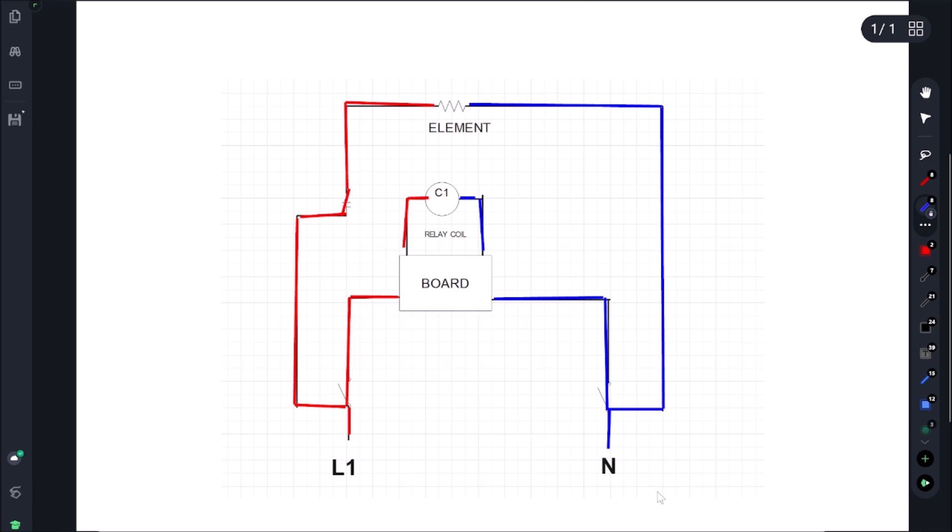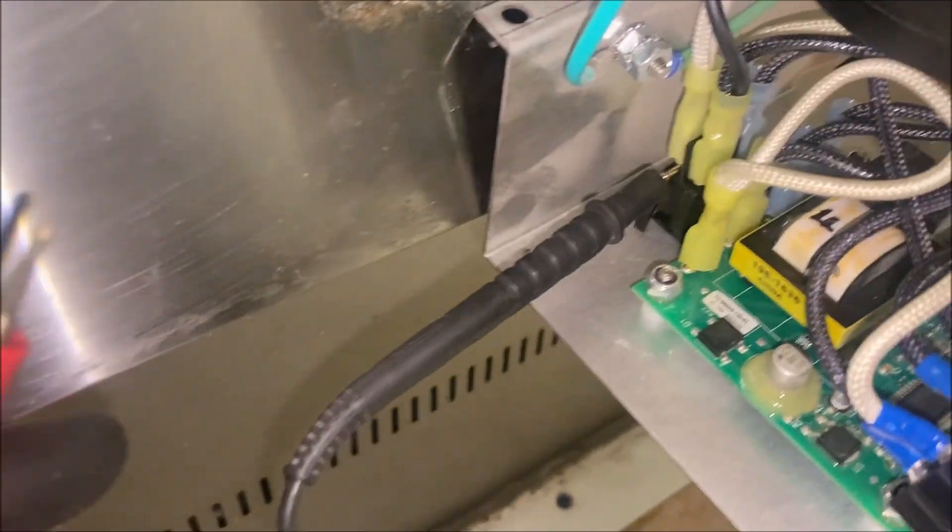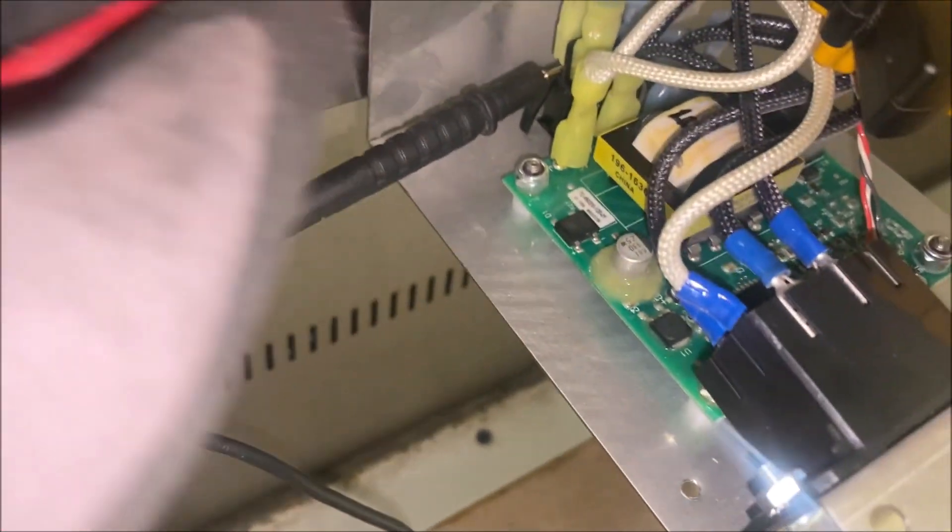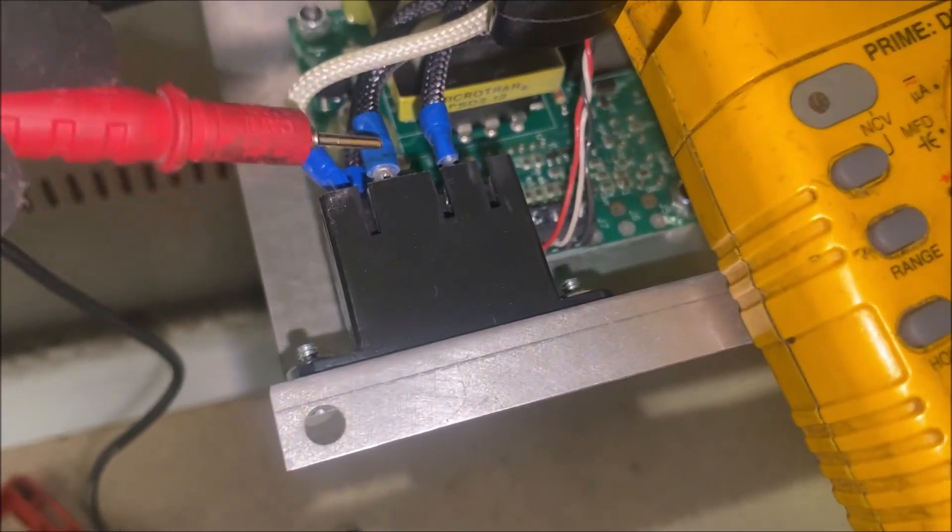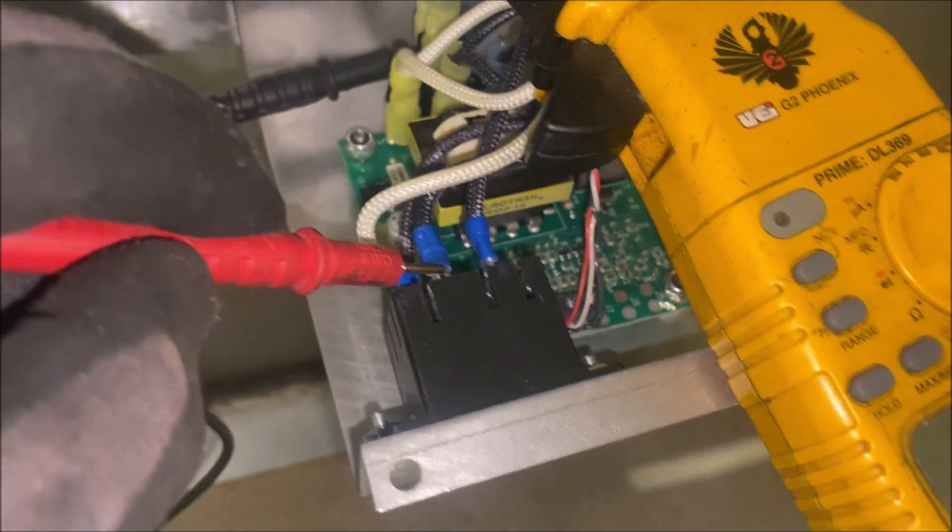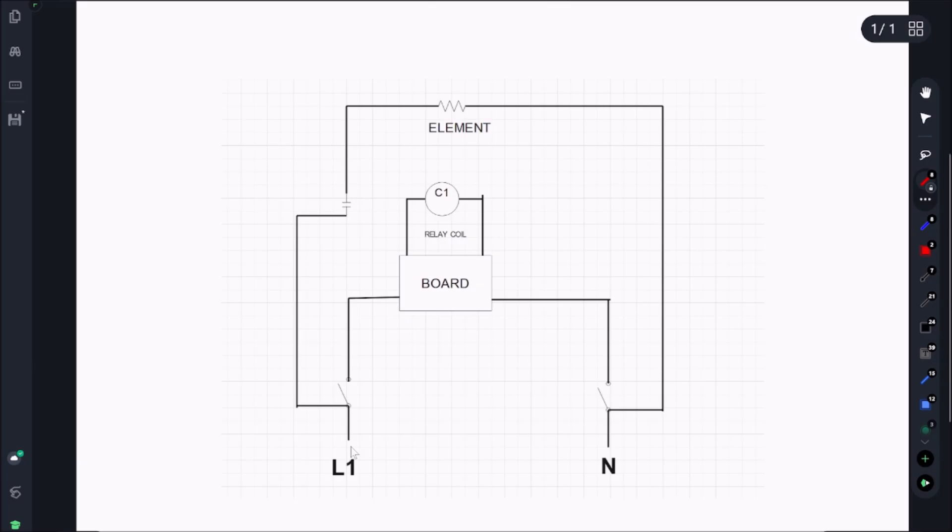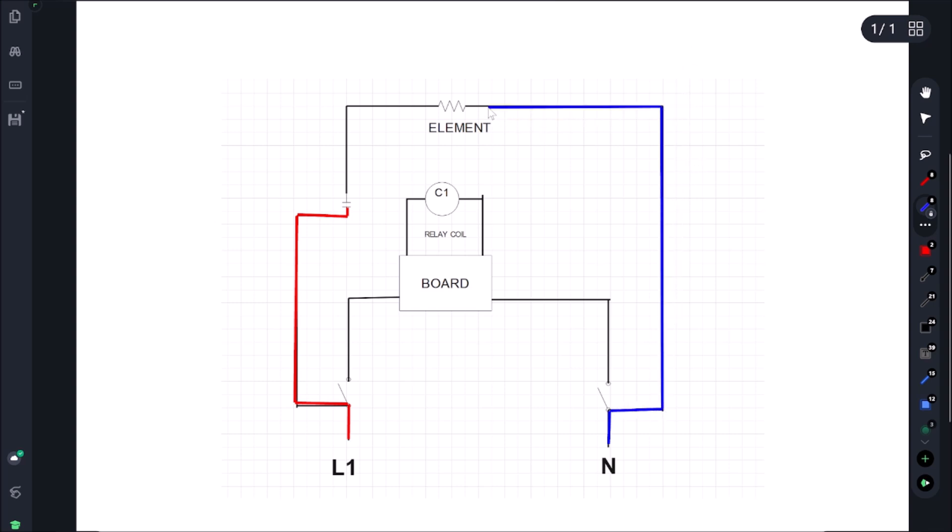So let's get our meter out and troubleshoot and see what's going on. Come off our incoming line and we're going to check power into our relay contact. We are getting 115 volts there. Alright, so with our switch off we're coming through here, we have 115 volts right here. This side is going to be completed circuit because it's on the incoming side of the switch. The element will always have the neutral hooked up. So let's go test this relay and see if it's stuck closed.